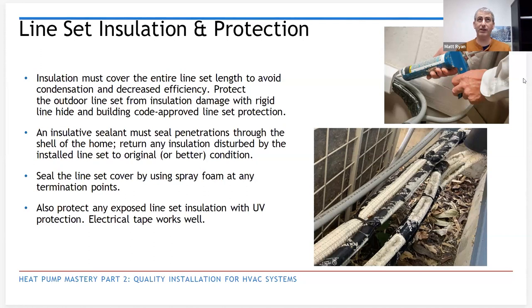Larger, like coming through a foundation vent, carrying some extra screen with you to seal up any oversized holes. And there's a steel wool product also. I've used that before as well. It helped where there are rodent issues. We've all been in that house where we know there are rodent issues, some steel wool behind some caulking or weatherproofing agent. When that's all retrofit, I guess when we're talking new construction, there's a lot of good products out there. Aerex is probably one of my favorite ones. They've got a lot of different products for line set penetrations. They'll actually have rubber boots that you can tighten down. It's another note to make for future presentations to have something in there for that.